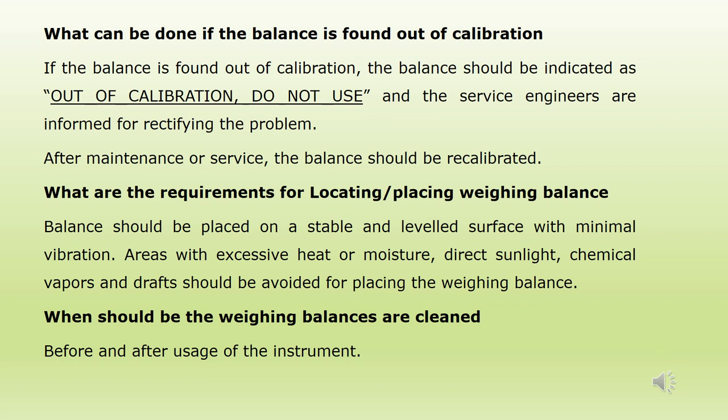What are the requirements for locating or placing a weighing balance? The balance should be placed on a stable and leveled surface with minimal vibration. Areas with excessive heat or moisture, direct sunlight, chemical vapors, and drafts should be avoided. When should weighing balances be cleaned? Weighing balances should be cleaned before and after every usage.